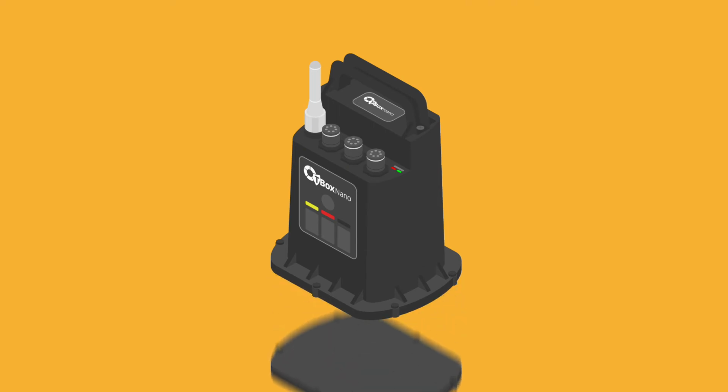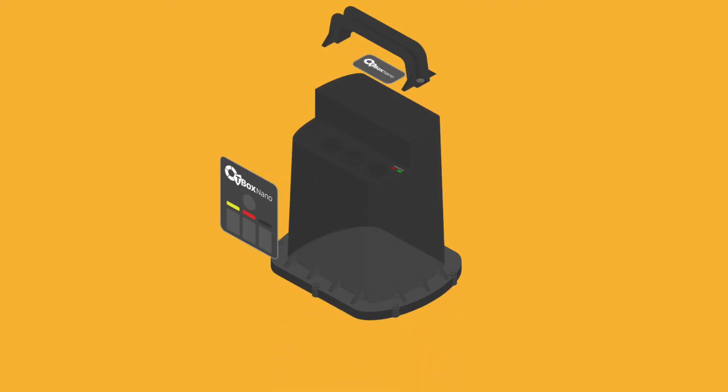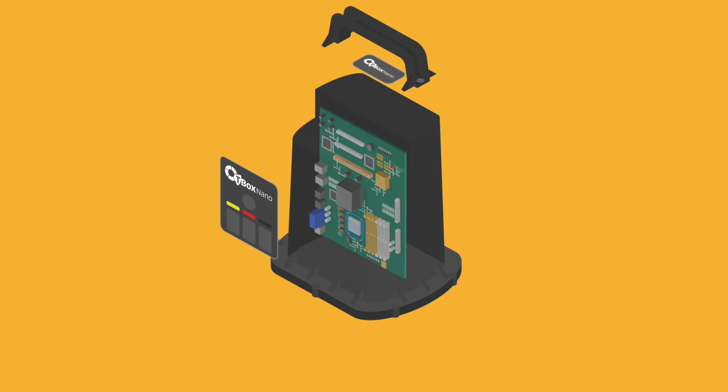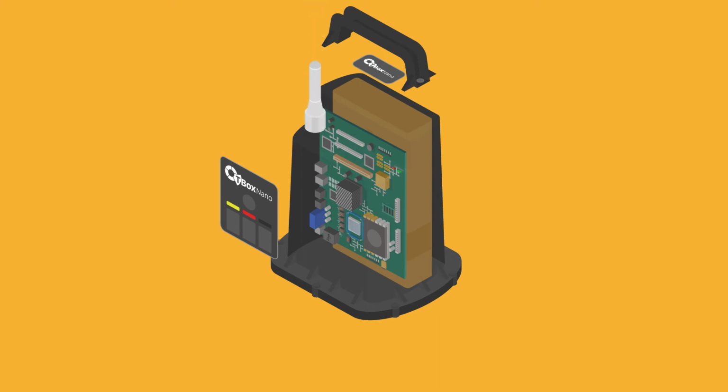Here's the clever bit. Let's take a look at what's inside. A powerful Kinetis K66 ARM Cortex M4 processor. 8 MB flash and 4 MB SRAM memory, expandable by SD card. Support for Modbus, DNP3 and IEC 60870-5-104 communication protocols. USB 2 for local programming. A 19.2-volt DC lithium battery. 3G wireless M2M communications. 1 digital output, 4 digital inputs, 3 analog inputs, and 1 RS485 serial port.